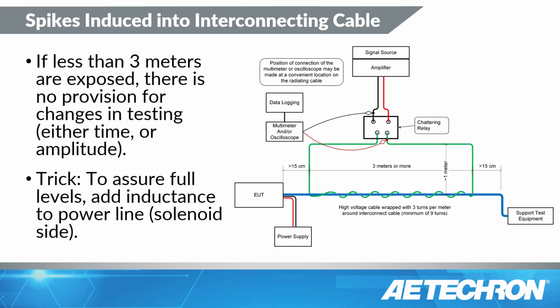Now, in a situation where you are testing a shorter wire, you may have some difficulty here, because the only time you really can expose less wire is if your cable is shorter on the aircraft. You really have to expose 3 meters of wire, and the reason why is because it's difficult to increase the voltage on this thing. However, I do have a couple of tricks. People have had some trouble on certain relays obtaining the full 600 volts or getting enough spikes over 600 volts to perform the test. One thing you can do, and let me show you what's going on with this relay.